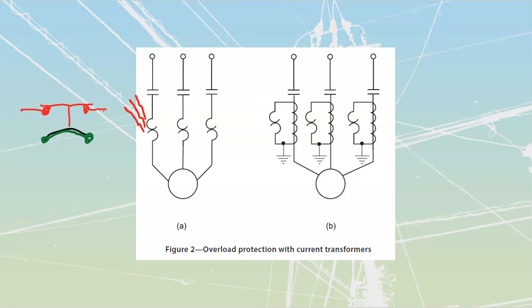When I take those leads out, I'm going to run them to my motor control circuit. So wherever that motor control circuit is, this thing is going to get run through. And these are going to have specialized terminal designations. We'll cover that later on in depth in motor controls. But as I heat up, this strip is going to bend, and what can happen is it can bend far enough up that it is going to pop that connection loose, which would be telling me that I've had too much current traveling through here, because too much current has resulted in I squared R, too much heat. And too much heat has opened that circuit and has shut that motor down for safety.